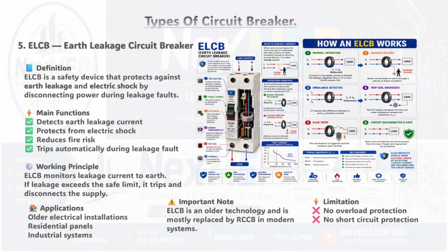So what exactly is an ELCB? It's a safety device that protects you and your electrical system from earth leakage and electric shock. The moment it detects leakage current flowing to the earth, it trips and disconnects the power supply automatically. Now, how does it actually work? The ELCB continuously monitors the current. When some current escapes through an unintended path, like through a person or faulty insulation, instead of returning normally through the neutral, that's called leakage current. The ELCB detects this imbalance and trips immediately.